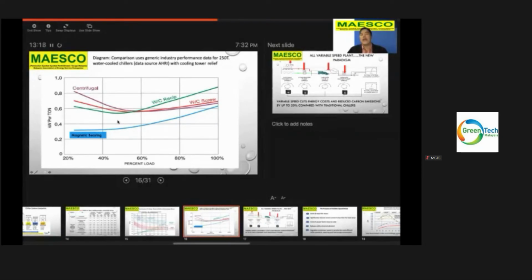If you are not very sure on the percentage or the loading that your building has, do buy a magnetic bearing chiller. A magnetic bearing can operate pretty well from 15% right up to 100%. But a magnetic bearing chiller is not cheap. They are more than 50 to 60% higher than a normal electric chiller. But one thing good about magnetic bearing is there's no oil. When there's no oil, it will help you in your operation as there will be less maintenance costs.